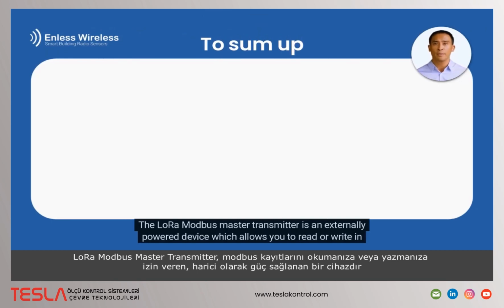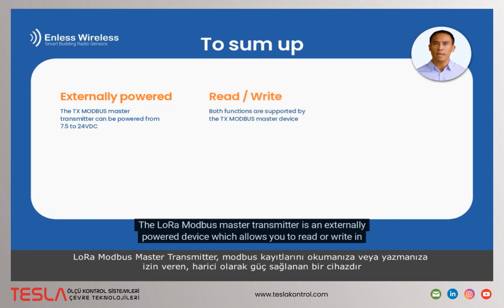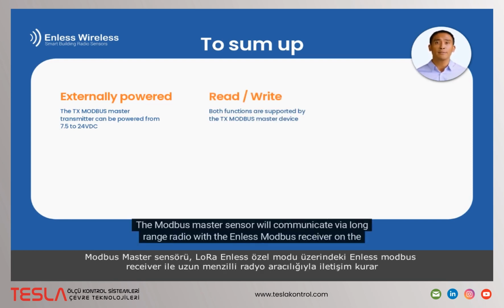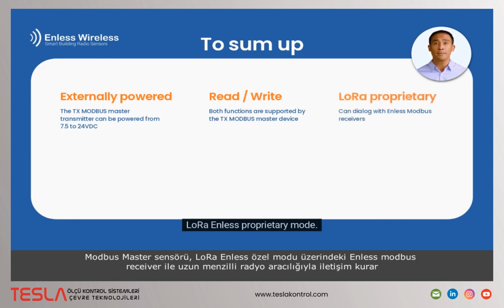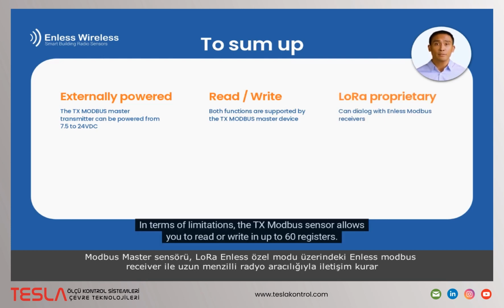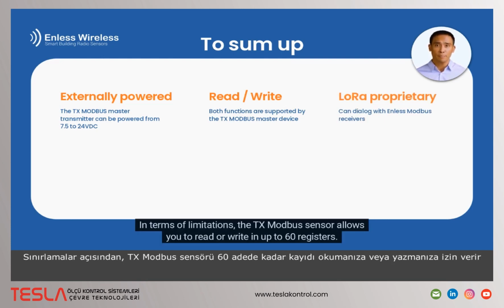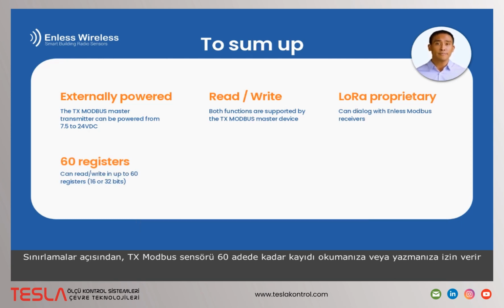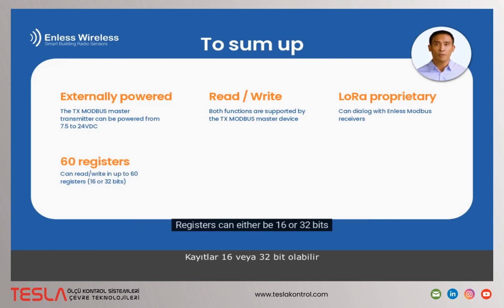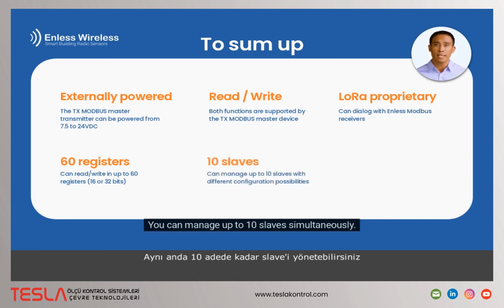To sum up, the LoRa Modbus Master Transmitter is an externally powered device which allows you to read or write in Modbus registers. The Modbus Master Sensor will communicate via long-range radio with the Enless Modbus receiver in the LoRa Enless proprietary mode. In terms of limitations, the TX Modbus sensor allows you to read or write in up to 60 registers. Registers can either be 16 or 32 bits. You can manage up to 10 slaves simultaneously.